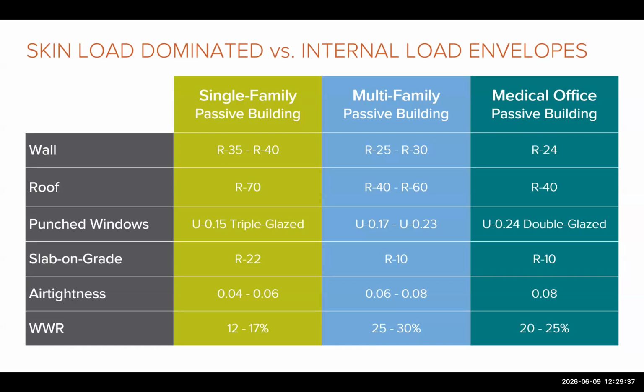So again, we're comparing three passive house types in Massachusetts: that single family, multifamily, and medical office. Single family homes are skin load dominated, which means they are envelope driven. Heat loss through the walls and windows is the main factor in driving total energy use for this building. And that also means that it requires more insulation. So you can see that the wall has between R35 and R40. Whereas a medical office building is internal load driven, equipment and activity generate a lot of that heat. That heat helps warm the building, and then it allows for lower insulation levels, such as an R24 for the walls. And it also allows us to do a really high performing double glazed window, which is a 0.24 compared to a 0.15 triple glaze for a single family home.